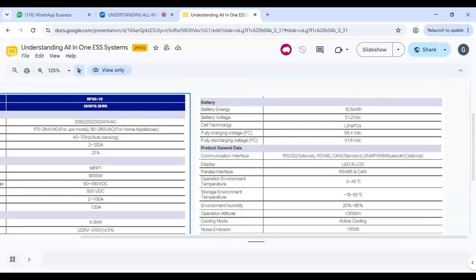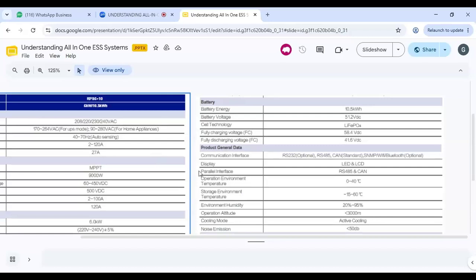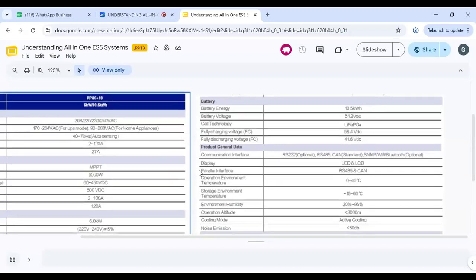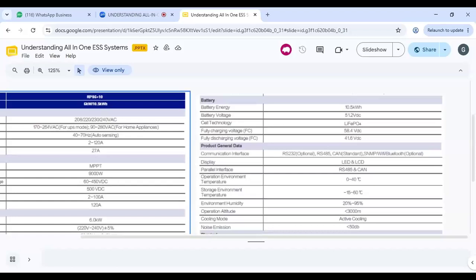Battery voltage is 51.2 volts. We'll see in this one, as the capacity of the inverter is increasing, the battery voltage is also increasing to that voltage level, which is normally 48 volts for this type of battery that has 51.2 volts. Then the technology is the same, which is LiFePO4. Fully discharged voltage is 41.6, while fully charged is 58.4 volts.